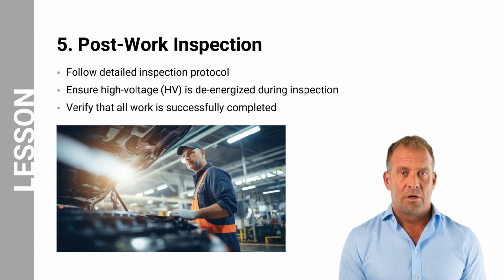Number 5, post-work inspection. Perform a final inspection to confirm everything is in order and safe for operation. This protocol should include visual checks, such as loose fasteners or anything that appears out of place, functional checks, such as testing sensors, and safety checks, such as lockout or tag-out procedures. Ensure that the high-voltage system remains de-energized throughout the post-work inspection.